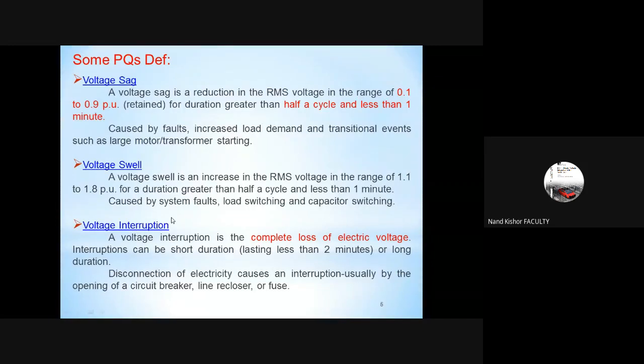And the next one is the voltage interruption. This is basically the complete loss of electric voltage. These interruptions can be of short duration, less than 2 minutes, or it could be for a longer duration in some cases. Disconnection of electric power will result in interruption. Usually it is by the operation of a circuit breaker, that is the opening of a circuit breaker, line recloser, or the fuse. So that way, it may lead to some kind of voltage interruption in the signal. Move to the next slide now.